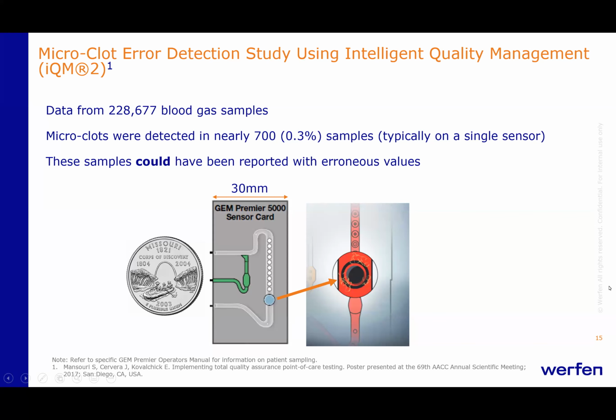So the microclot error detection study using intelligent quality management was published in 2017. The GEMS record all the sensor values for both the patient samples and for the process control quality checks. They checked data from over 228,000 blood gas samples, and they saw that microclots were detected in approximately 700 samples, which is about a 0.3% rate. And typically the microclots were only on a single sensor on these samples.